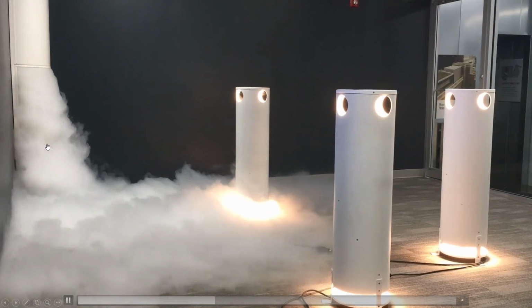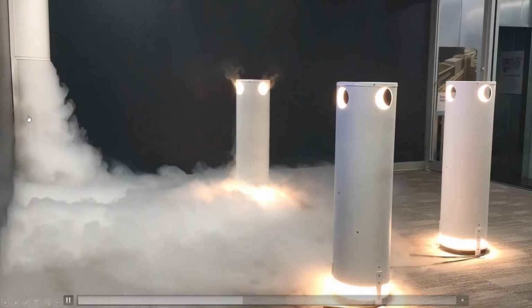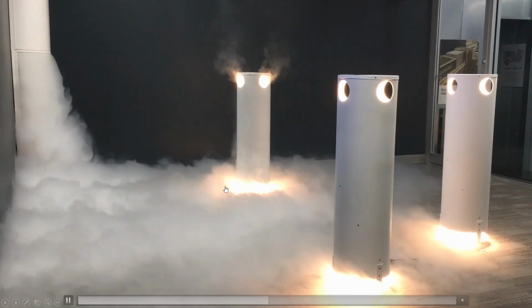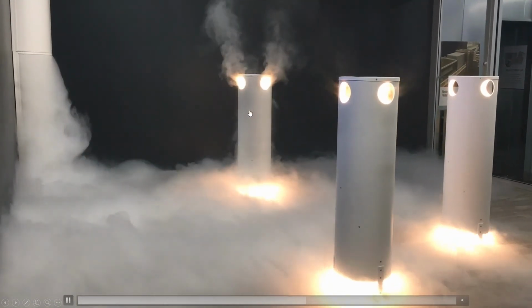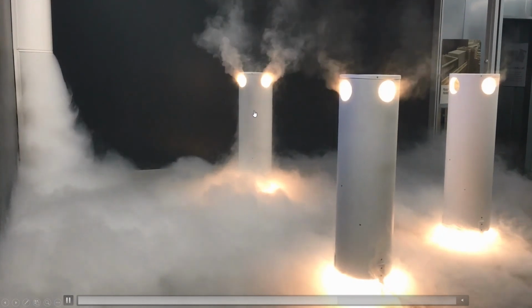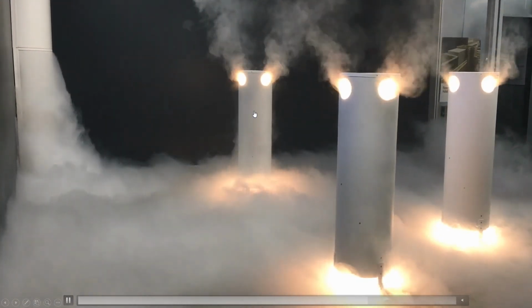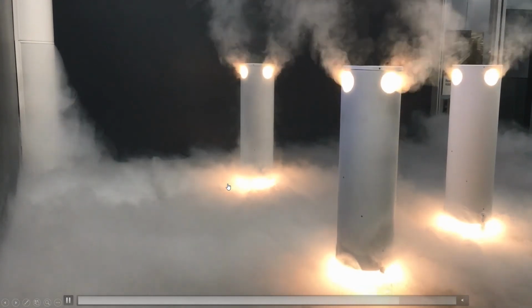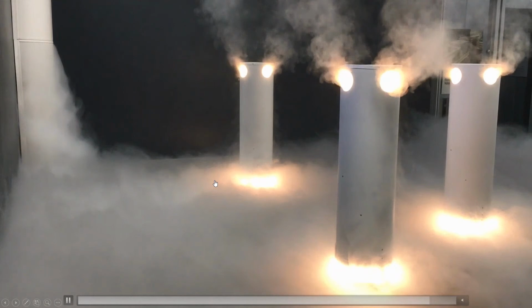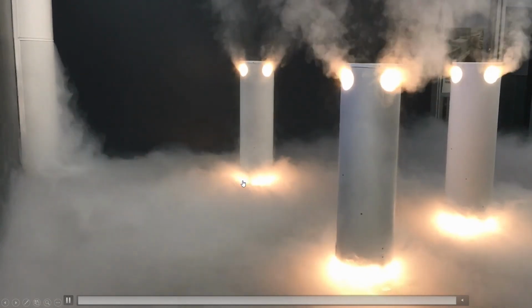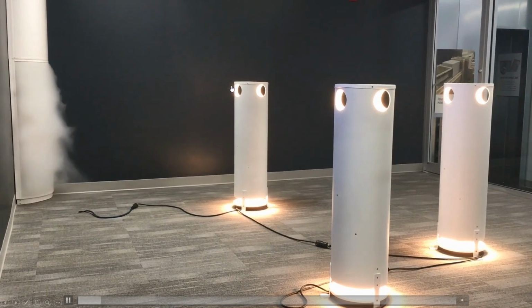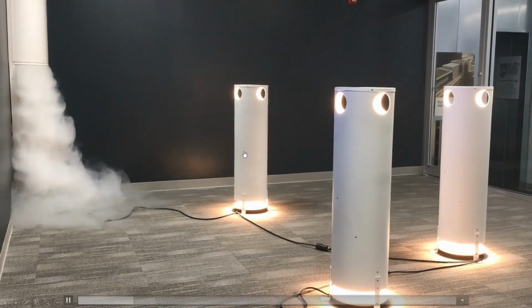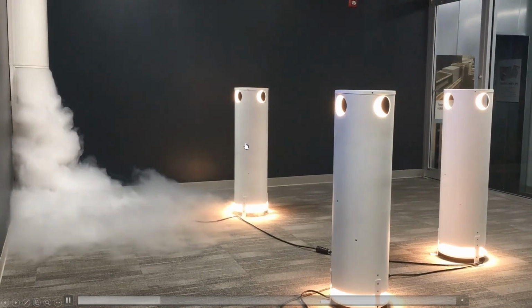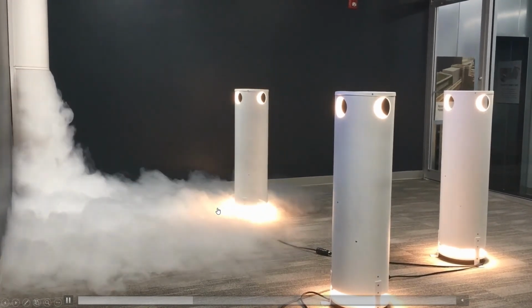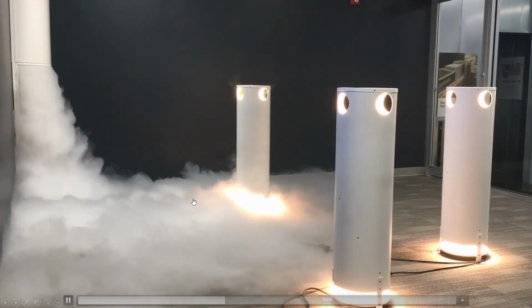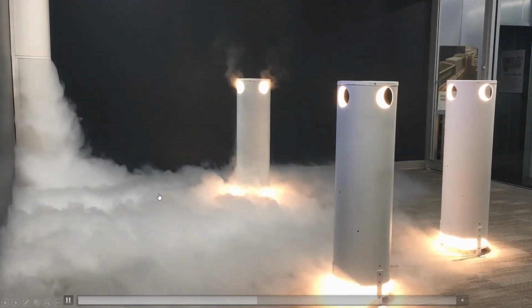You can see the air's coming out around 40 feet per minute, nominal across the face, and it's seeking out the various thermal plumes. In the case here, we've got our thermal mannequins, which represent a typical sensible load of an occupant, student, or adult. You can see the air is moving very slow, even across the ankle region, much slower than across our normal thermal plume velocity. We're naturally used to feeling quicker velocities across our body from the thermal plume, compared to the velocity across the floor plate, a foot or two away from the diffuser.